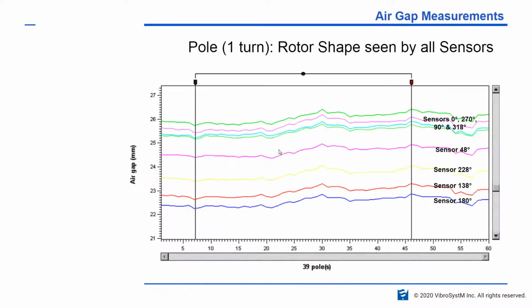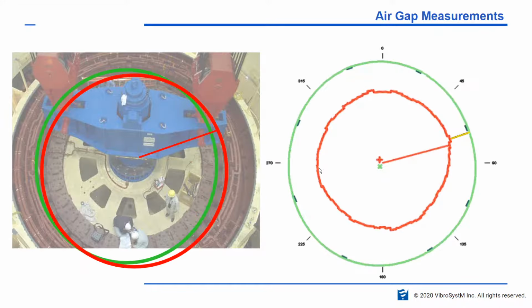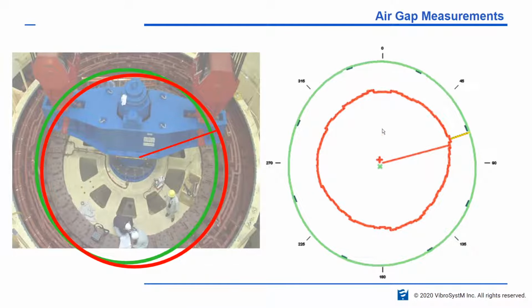Here we have the same reading from 1 rotation that can also produce a polar graph. So we can see the shape of the rotor and the shape of the stator and also their positions, one compared to the other. And as I mentioned, you can see in cases where the air gap is too small on one side, when you excite, the unit will go into that direction. And you can see this type of information very easily with 1 measurement of the unit, and you can see the interactions between the rotor and the stator shapes and or positions.